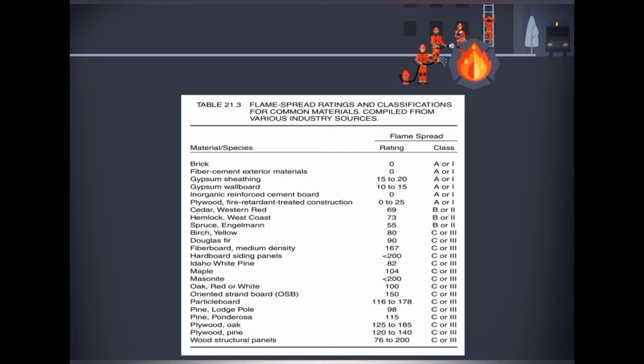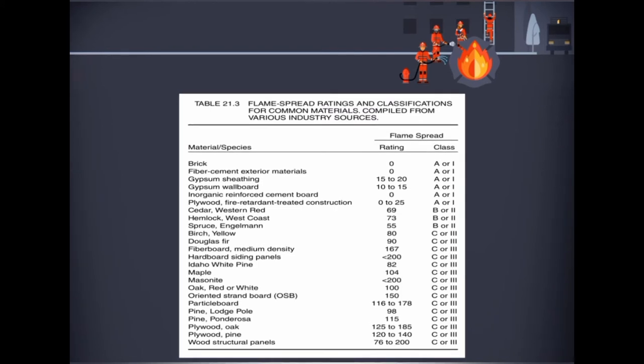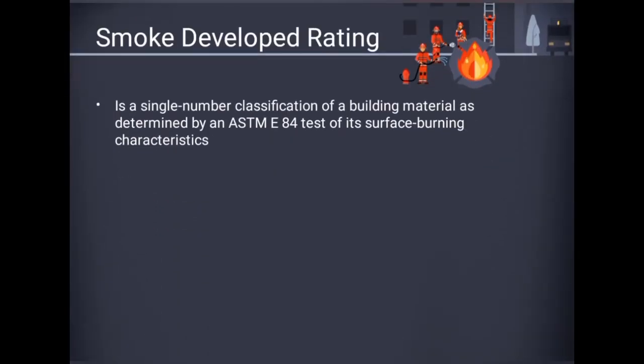In general, inorganic materials such as brick or tile are Class A materials. Reconstituted wood materials such as plywood, particle board, and hardboard are Class C. Most wood products have a flame spread rating less than 200 and are considered Class C material. A few species qualify as Class B materials. The smoke developed rating is a single number classification determined by an ASTM E84 test of surface burning characteristics, expressed as a ratio of the smoke emitted by a burning material to the smoke emitted by the red oak standard material.